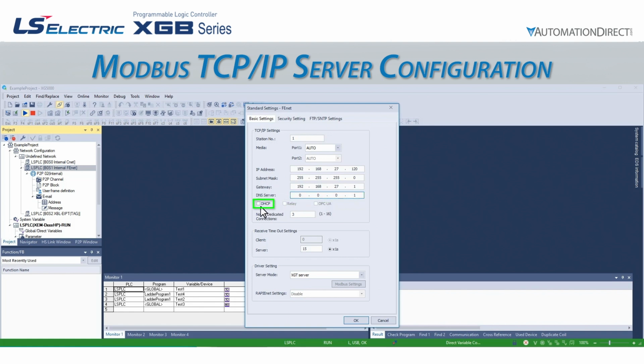We can also use DHCP to allow a local DHCP server to automatically configure the IP settings for the PLC. Using DHCP can lead to potential network routing or unintentional IP address issues, so be careful when enabling this setting. Once we configure these settings, we are ready for the Modbus TCP configuration.